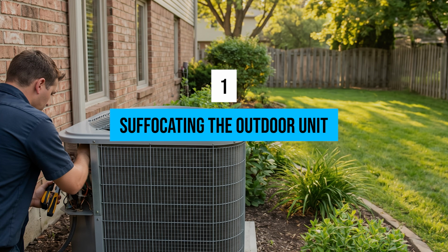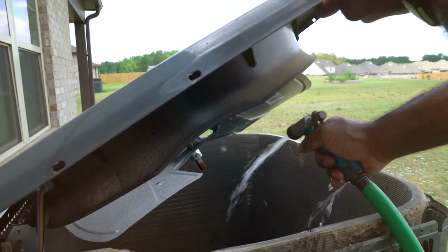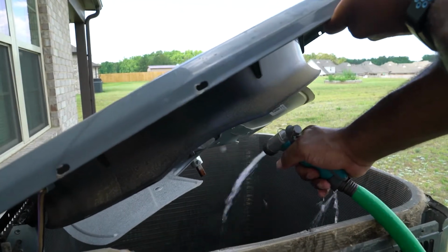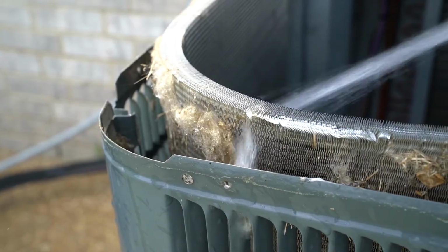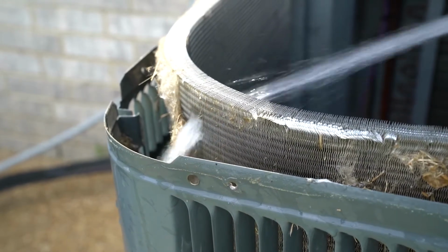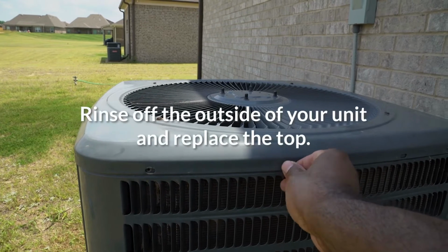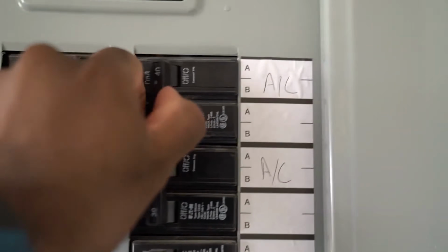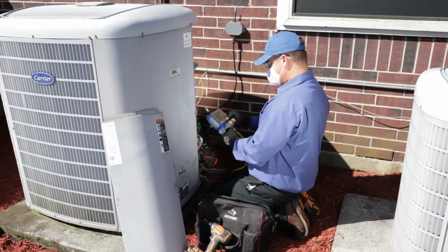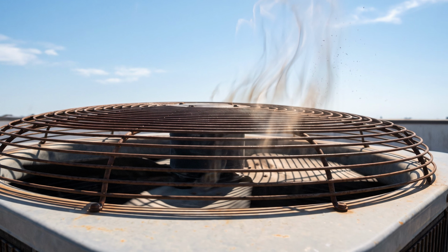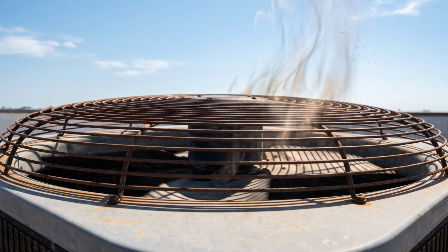Number 1. Suffocating the outdoor unit. The last mistake happens entirely outside. Every central AC system has a large metal box sitting in the yard. This is the condenser. Its only job is to take all the heat that was removed from your house and dump it into the outside air. For this heat transfer to work, the condenser needs massive amounts of fresh air to flow through the metal fins on the sides and exhaust out of the top.